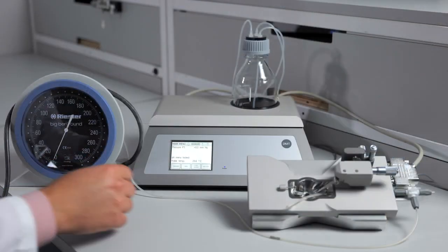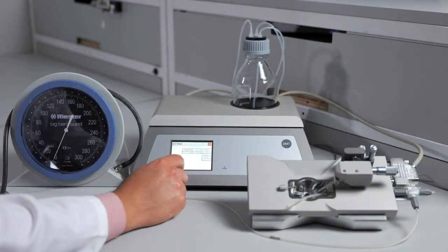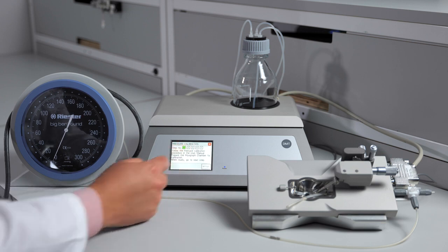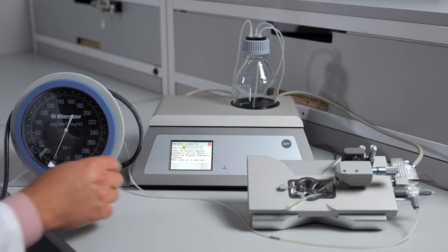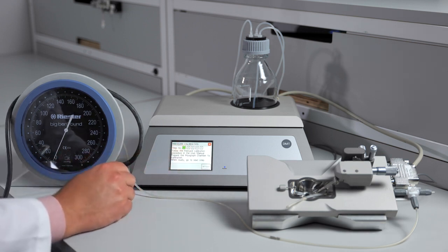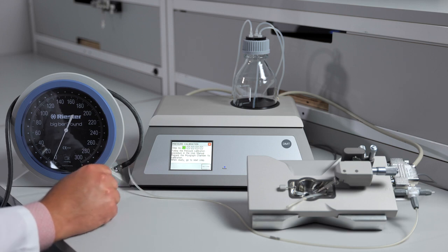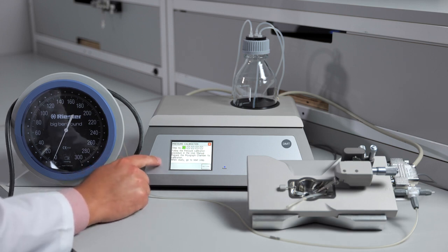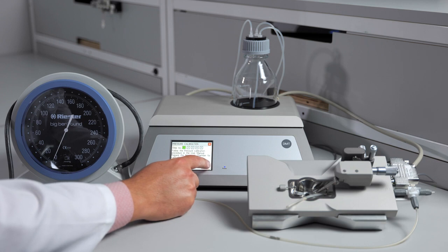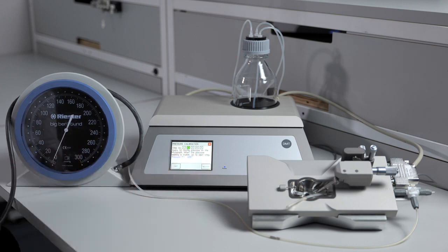To start the pressure calibration, go into the settings menu and select pressure calibration. The first page will tell you to follow the instructions in the user manual. However, instructions are provided on the screen itself. Select Next Step. Step 2 asks you to add 50 millimeters of mercury into the chamber. Use the big ben manometer to add the pressure.